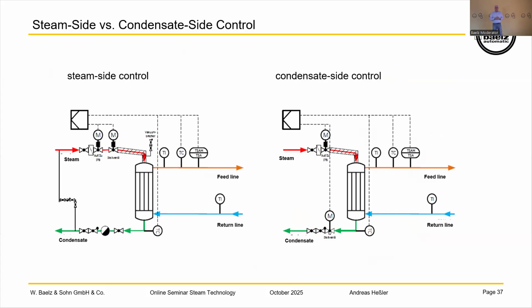On the left picture you see the steam side control, which means you need a control valve in the steam inlet to control the temperature on the secondary side. And with condensate control, you're not controlling the steam, you're controlling the condensate, whereby you control the outlet temperature on the secondary side.